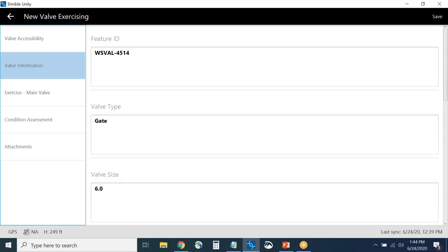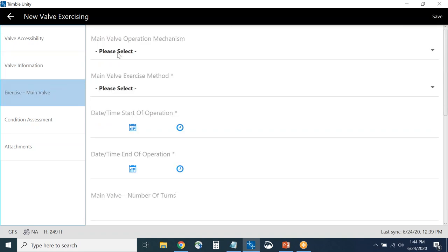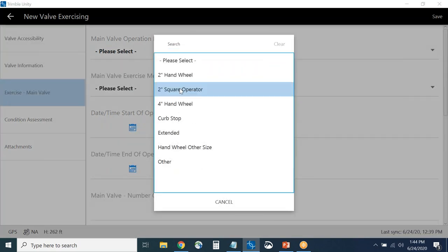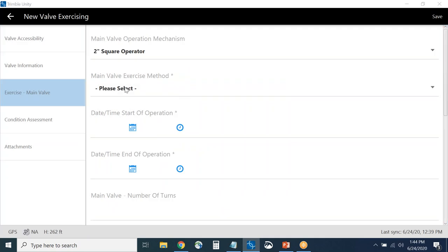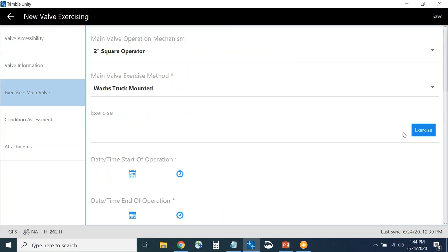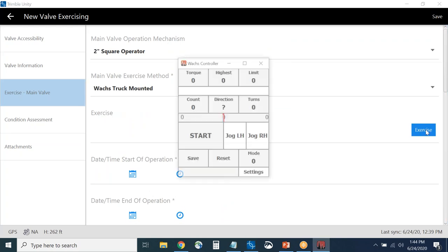On the valve information form, if I needed to update any attributes I could do so, or leave it alone — it's mainly so the field person knows they're at the right valve. Then I get to the valve exercise screen, where I specify how I'm performing the inspection: the mechanism is a square operator, and the method — if exercising by hand I select that, or if using a Wachs Truck Mounted I select that. Then I hit exercise to launch the Wachs Controller.